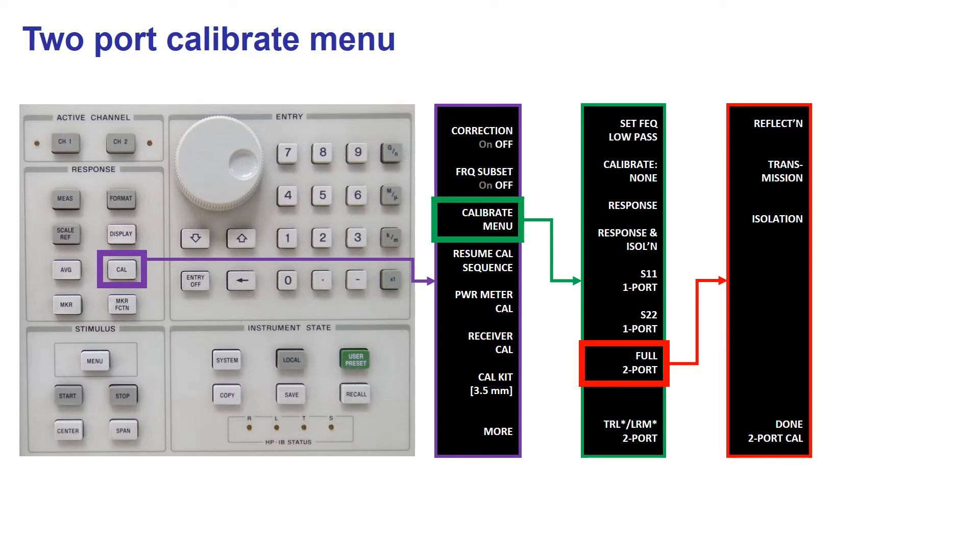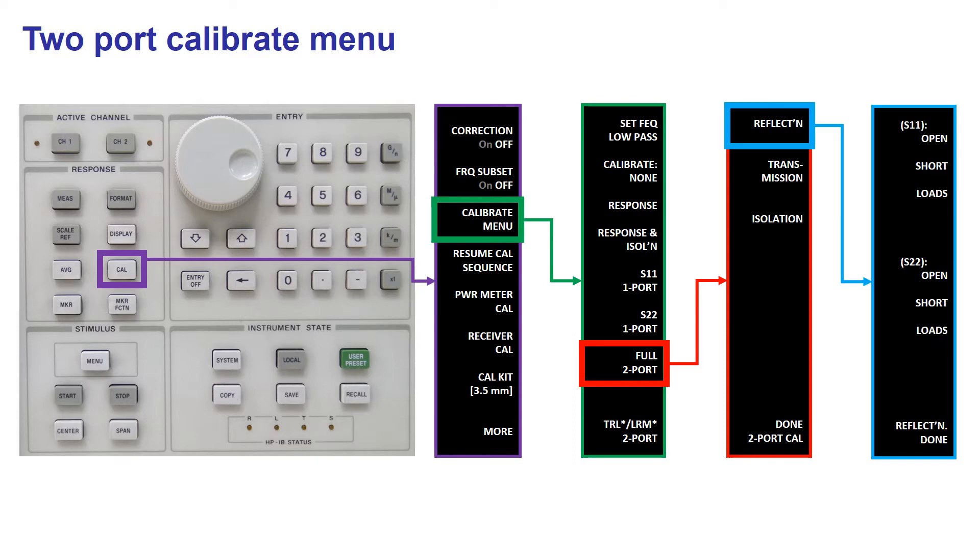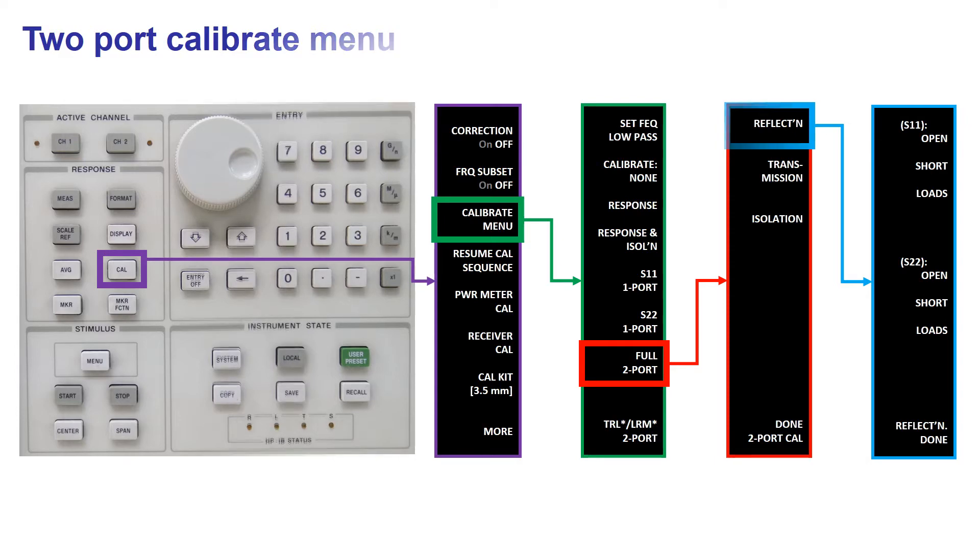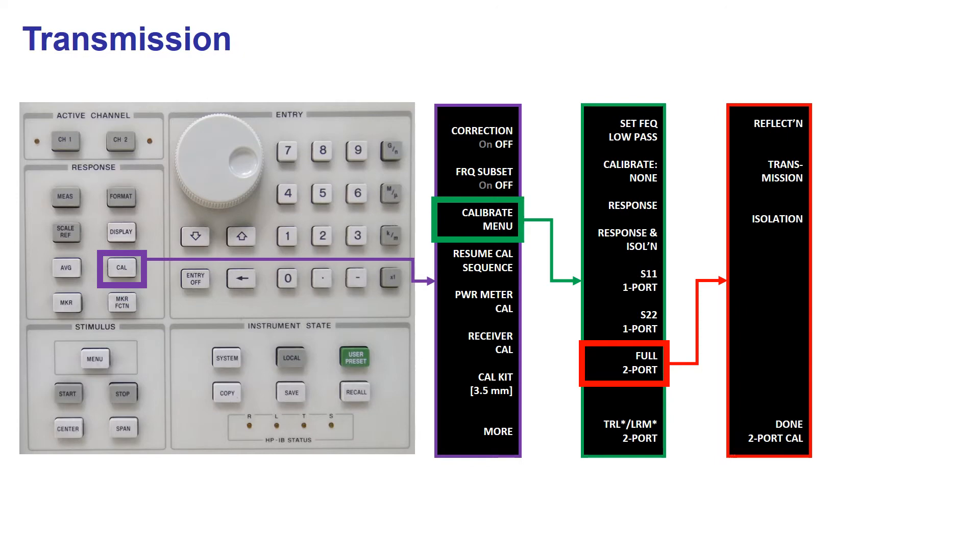We start with the first item, reflection, which leads you to a process similar to the one-port calibration we explained before, where you must connect the same standards at each port. Once you finish the reflection measurements, you press Reflection Done and with this you go back to the full two-port menu.